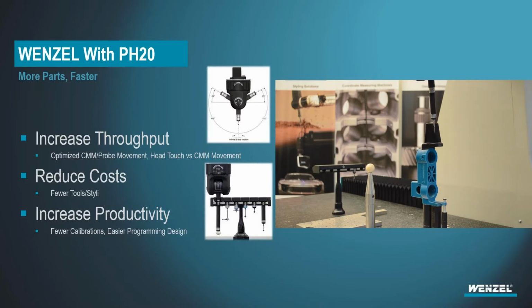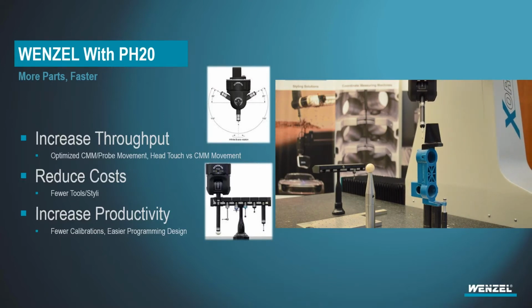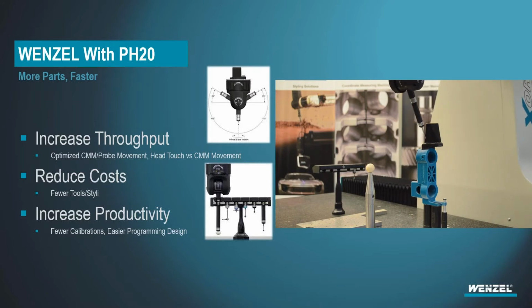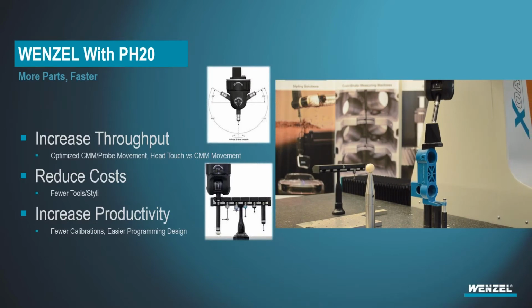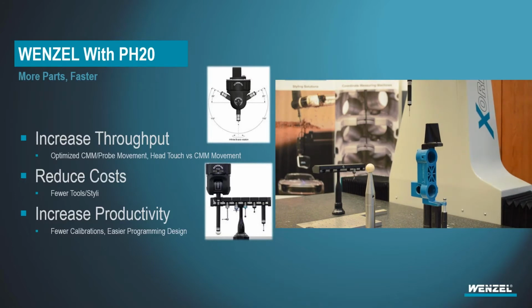PH20 can also handle a range of probes. It's not a one-trick pony. As you can see in this picture here in the bottom left, there are some different lengths. You can still have that sphere stylus. You can still have star probes or angle probes if you need even more flexibility to reach within a hole or a chamfer or something that you might need that little bit of extra positioning. You can fix the PH20 head into an angle and go ahead and take that measurement.